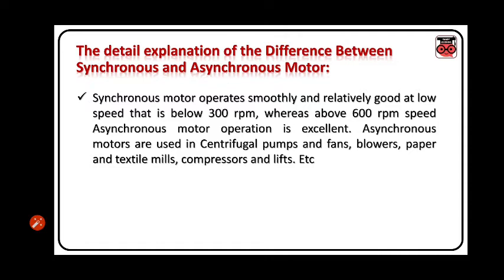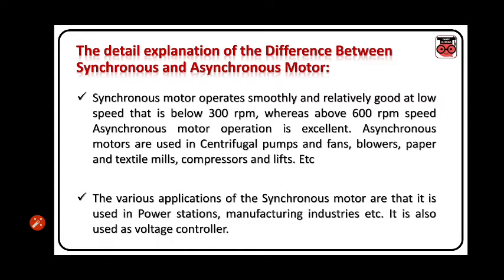Synchronous motor operates smoothly and is relatively good at low speed, that is below 300 RPM. Whereas above 600 RPM, asynchronous motor operation is excellent. Asynchronous motors are used in centrifugal pumps and fans, blowers, paper and textile mills, compressors, and lifts, etc. The various applications of synchronous motor include power stations, manufacturing industries, etc. It is also used as a voltage controller.